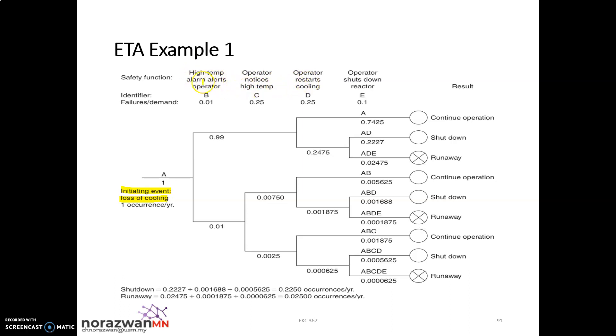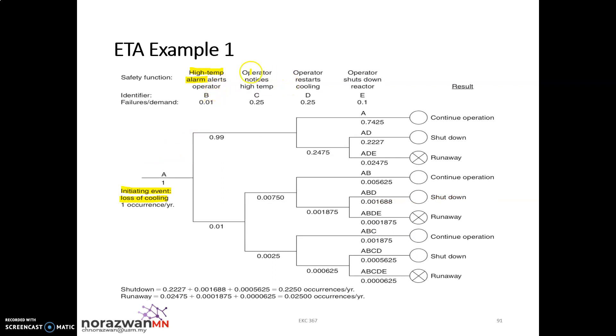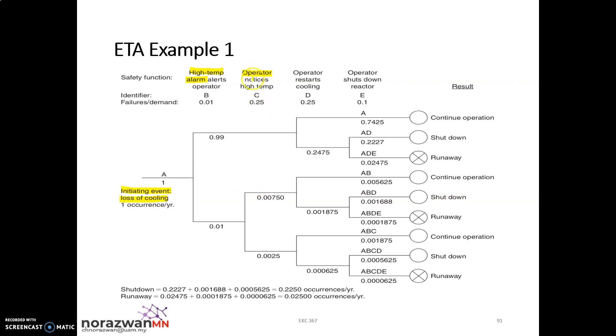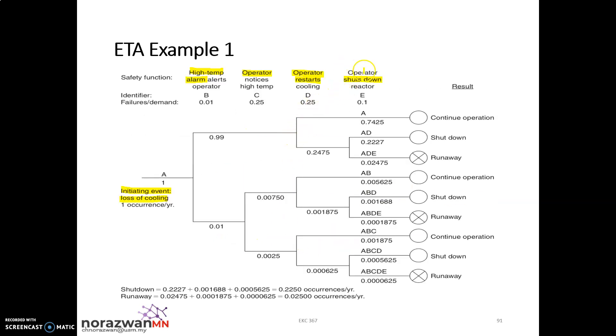The first safety function is the high temperature alarm alerting the operator. The second safety function is the operator — did the operator notice the high temperature alarm or not? The third safety function is the operator restarting cooling, which is the recovery step — does the operator restart the coolant flow after noticing the high temperature? The fourth and final safety function is emergency shutdown of the reactor.